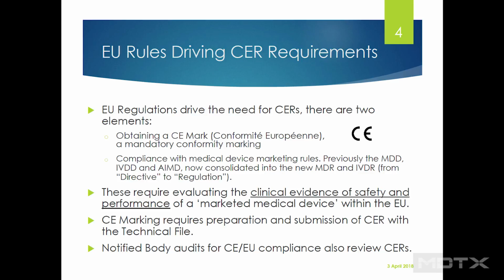It's also affecting the details. The MedDev guidelines are also being affected. There are guidelines that change independently on their own course, and then there are guidelines that are changing strictly in response to the regulatory changes. So we've had a transition to Rev 4, and Anne is going to be talking about that for the CER guideline, MedDev 2.7.1 Rev 3 to 4. We're going to get into the details, but just know that there could be more changes coming. This is never a fixed thing, so this is where they're at right now.